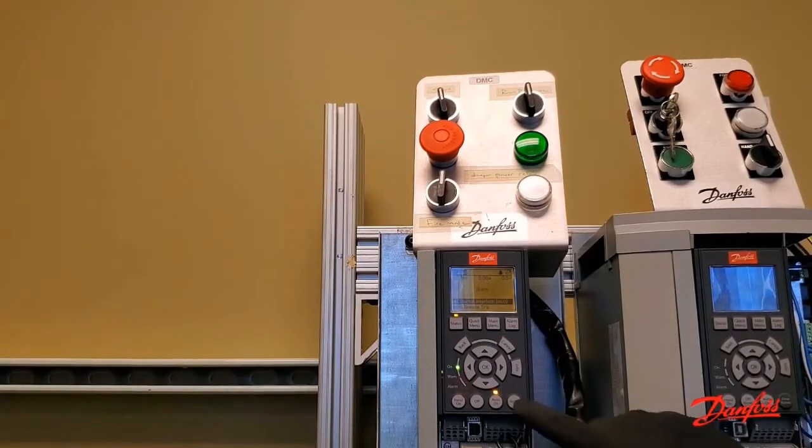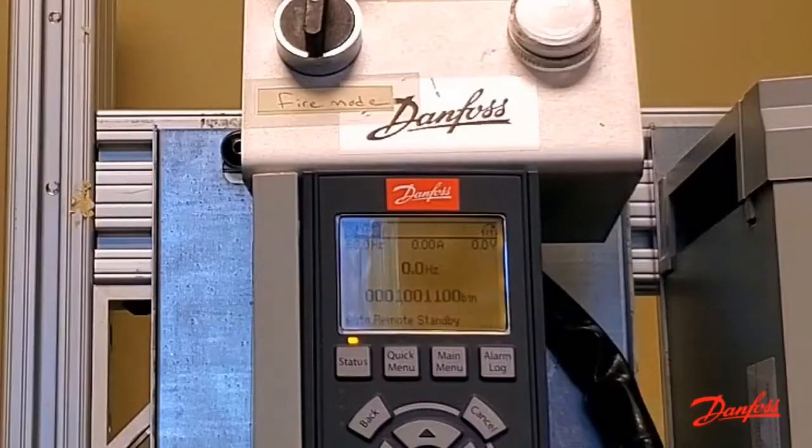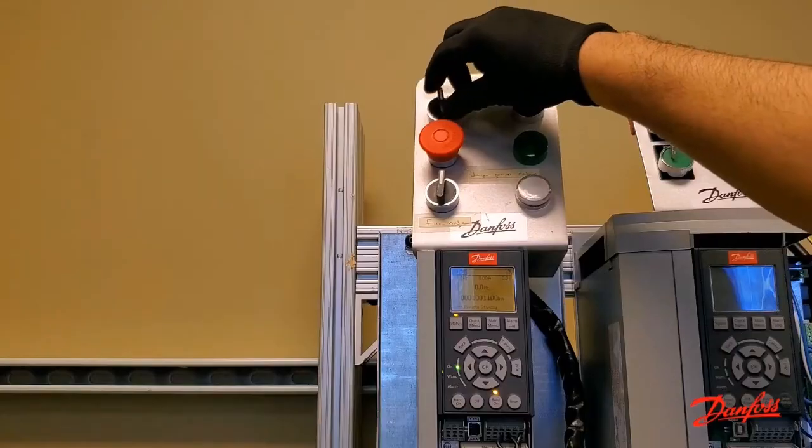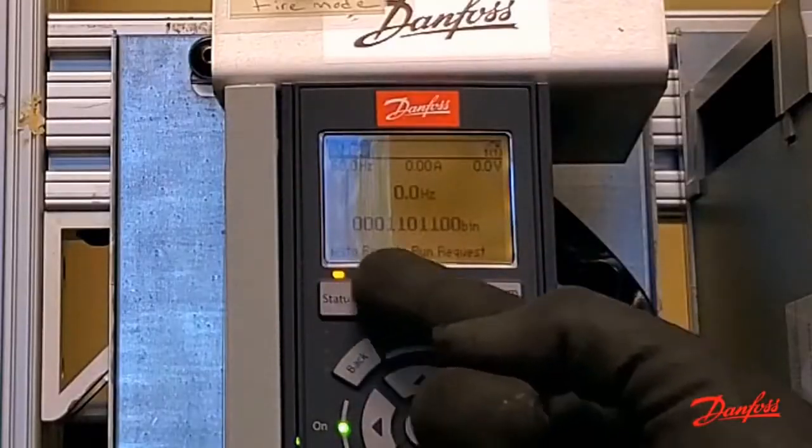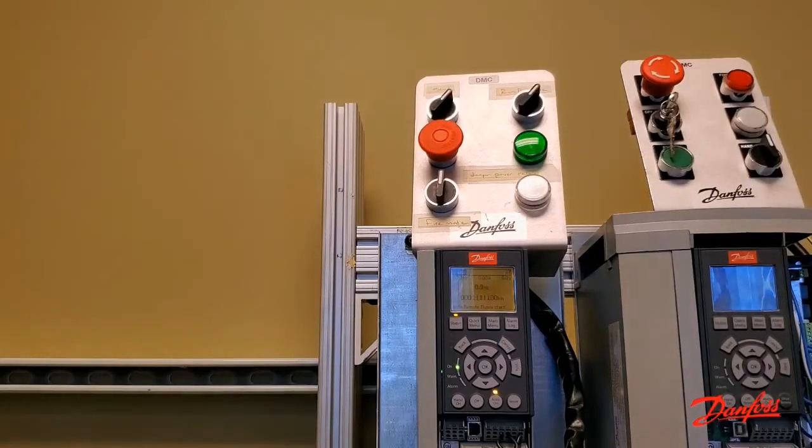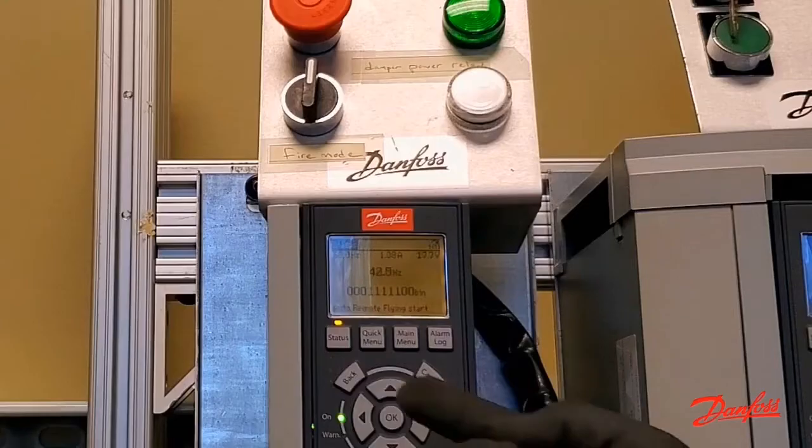Auto-remote standby means you're missing the run command. And auto-remote run request means you're missing the run permissive signal. All three of these signals are required for the panel to run in both drive and bypass.